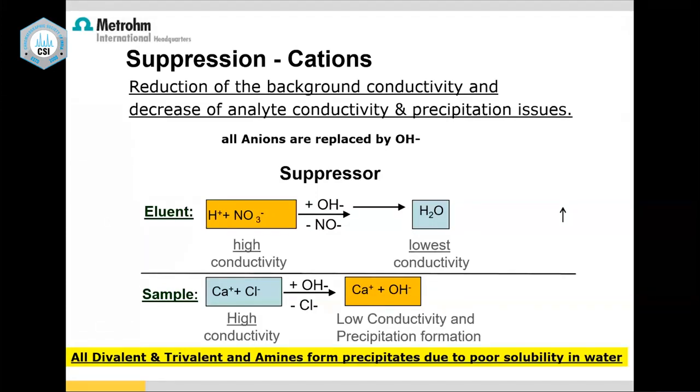So you may ask how to do cation analysis. That is why we employ nitric acid eluent, which is, let's say, for example, 3 millimolar. 3 millimolar nitric acid has around 900 microsiemens. There are some eluents like methane sulfonic acid, at the same 3 millimolar, which is being operated, but instead of 900 microsiemens, methane sulfonic acid gives you a conductivity of around 2000.